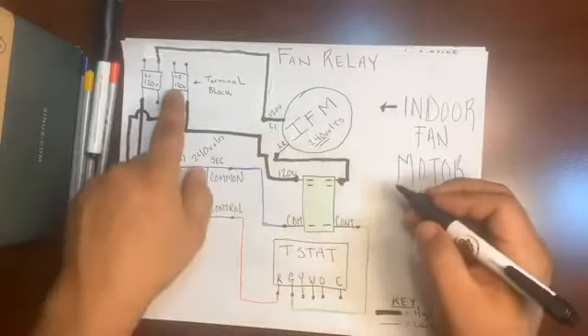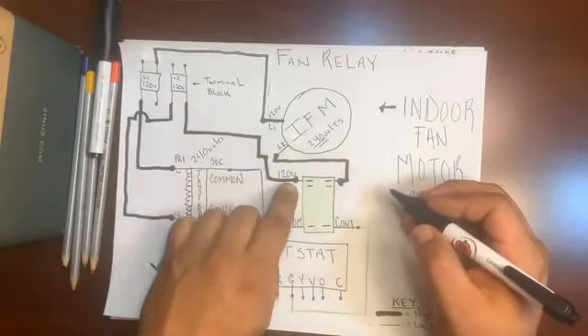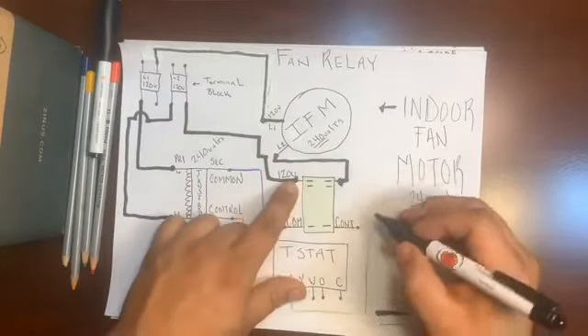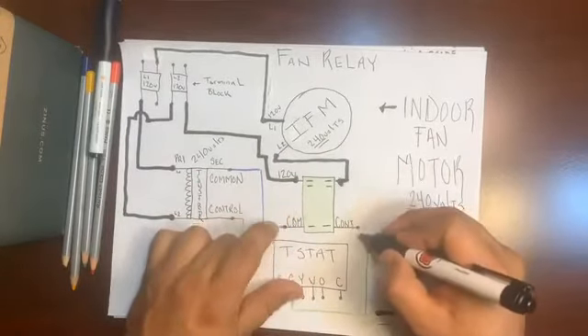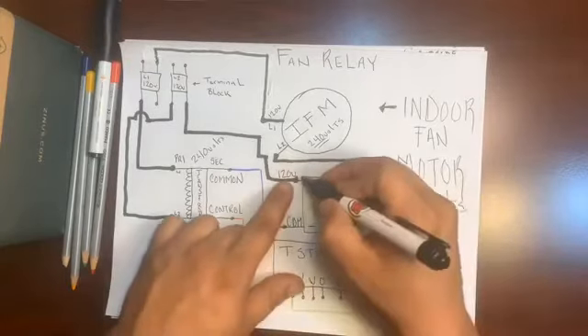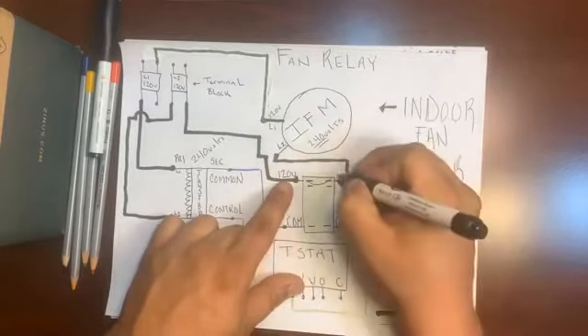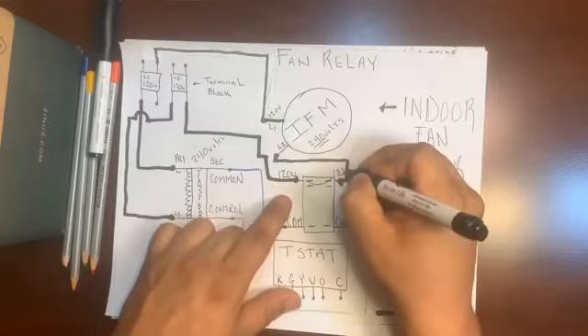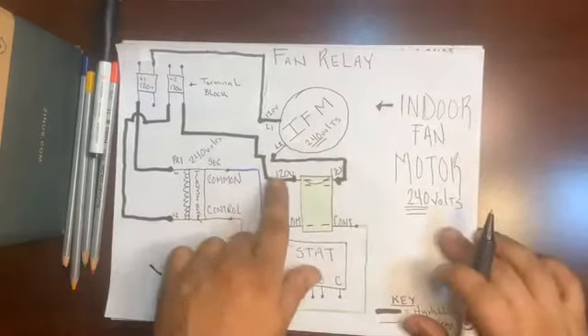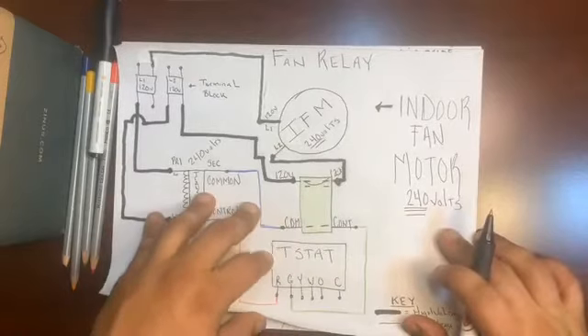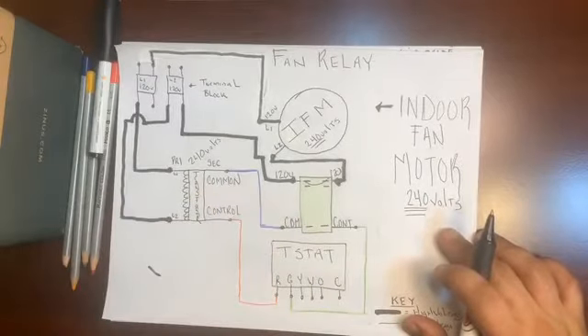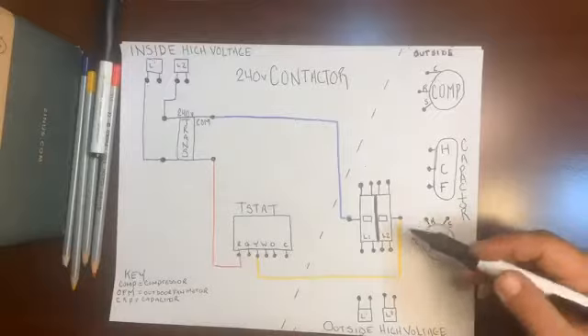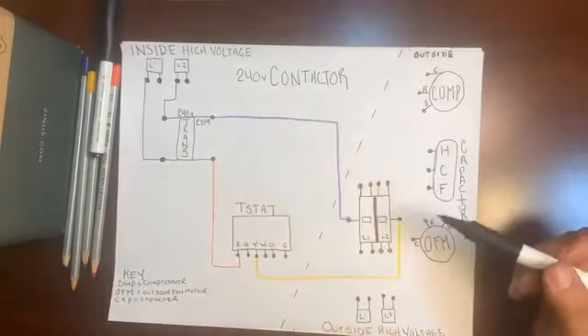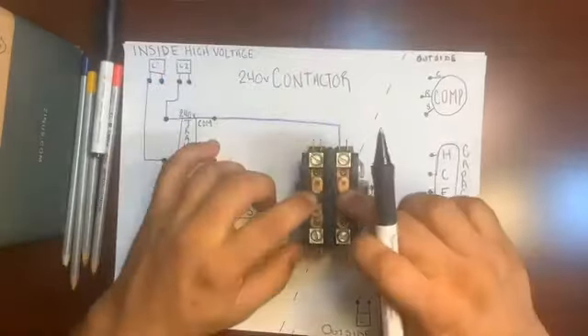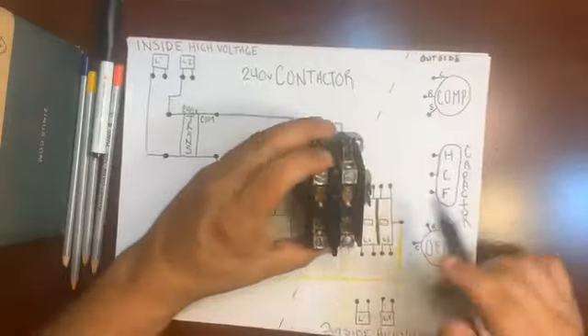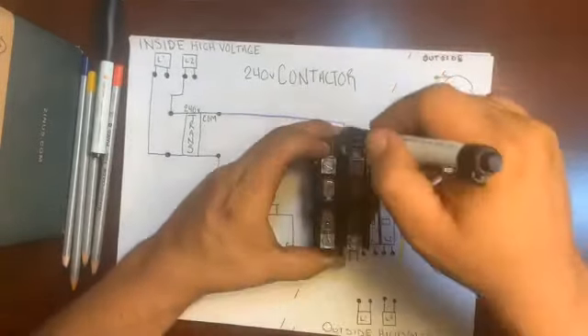So 120 volts leaves L2 and it stops here until 24 volts is supplied to the low voltage side of the relay, and then it's jumped through, and then 120 volts continues here. So every relay is going to split 120 volts, the heat sequencer and the fan motor relay, but the contactor is 240 volts. That's why there's two poles. This is a two-pole contactor, one pole, two pole. So we need 240 volts, 120 through each leg.